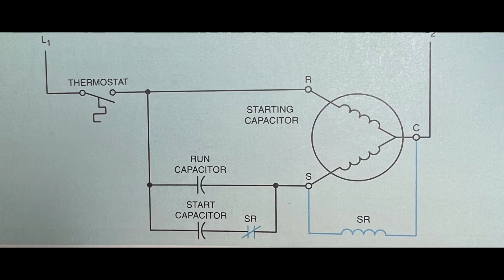Potential starting relay. The potential starter relay is used with a different type of split phase motor called the capacitor start, capacitor run, or permanent split capacitor motor. This type of split phase motor does not disconnect the starting winding from the circuit. Since the start winding remains energized, it operates very similarly to a true two-phase motor. All of these motors contain a run capacitor that remains connected in the start winding circuit at all times. Many of these motors contain a second capacitor that is used during the starting period only. This capacitor must be disconnected from the circuit when the motor reaches about 75% of the rated speed.